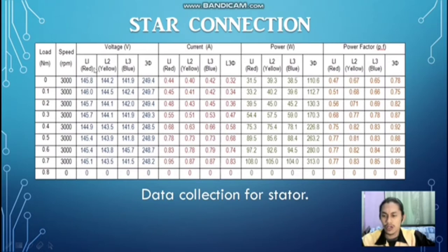First of all, we observe the voltage parameter. In this voltage parameter, there are single phase and three phase. The single phase value will remain the same when the load increases, approximately around 145 until 147. The three phase is also the same. It does not change when the load increases. The value will remain the same from 248 until 249.